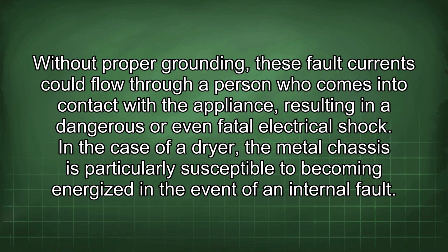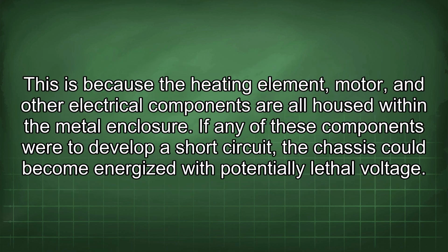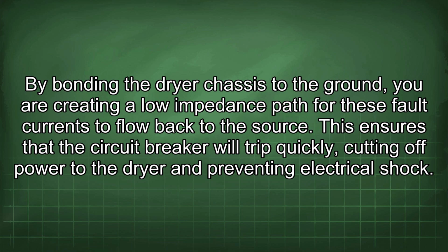In the case of a dryer, the metal chassis is particularly susceptible to becoming energized in the event of an internal fault. This is because the heating element, motor, and other electrical components are all housed within the metal enclosure. If any of these components were to develop a short circuit, the chassis could become energized with potentially lethal voltage. By bonding the dryer chassis to the ground, you are creating a low impedance path for these fault currents to flow back to the source. This ensures that the circuit breaker will trip quickly, cutting off power to the dryer and preventing the electrical shock.